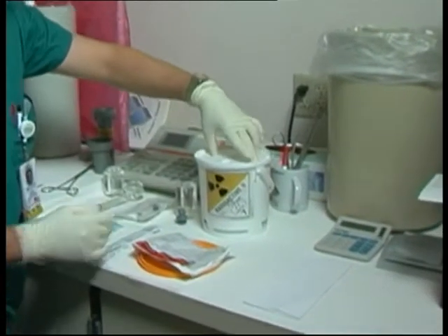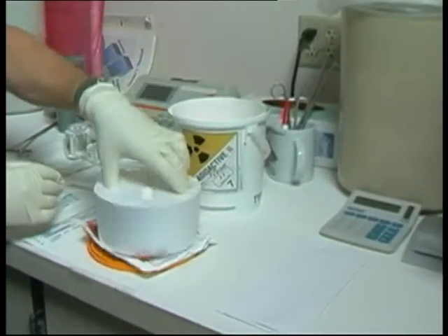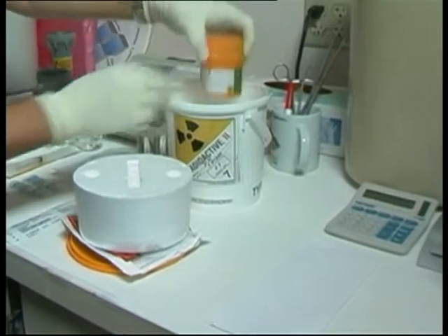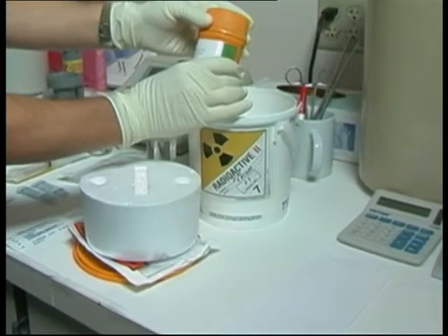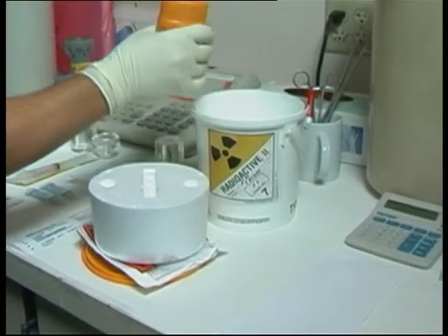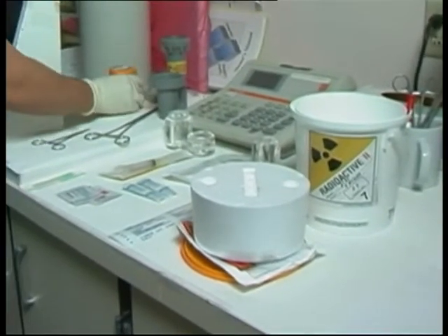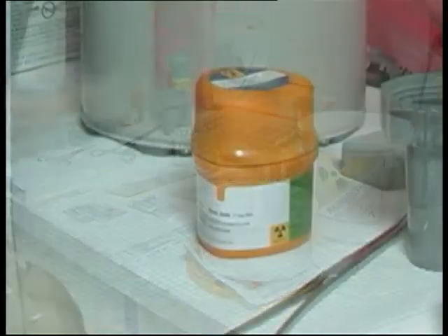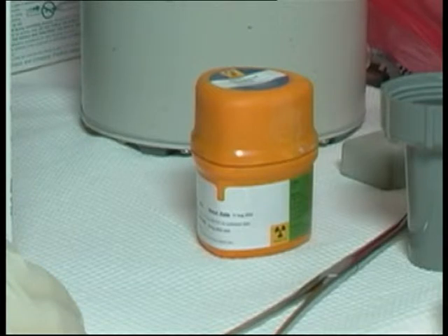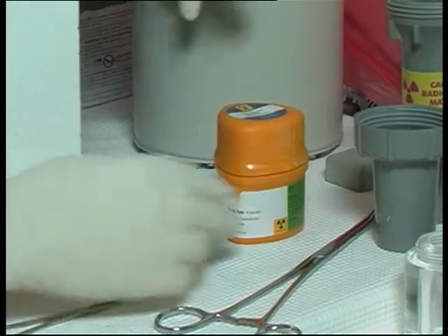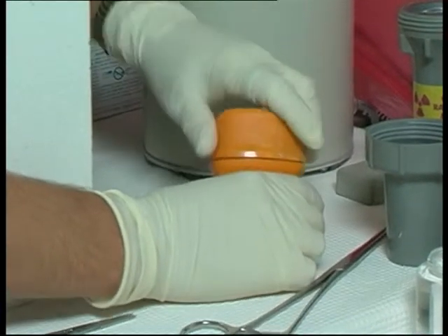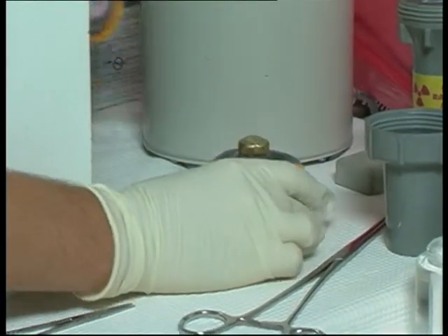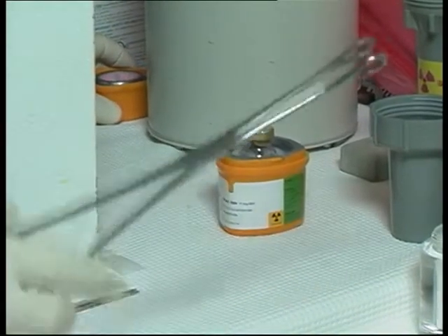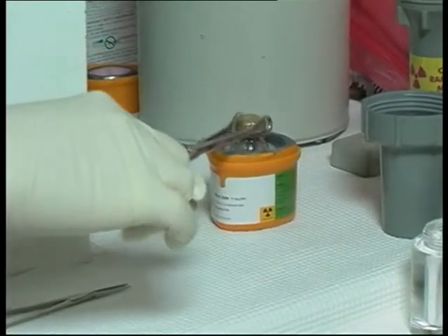SIR spheres will be shipped in an approved container. The SIR spheres shipping vial will be in a yellow lead pot to provide protection from radiation. Remove the lead pot from the shipping container and place it behind the L-block and acrylic shield. Check the label on the lead pot and vial to verify and confirm the calibration date is correct. Use tongs to remove the SIR spheres shipping vial and invert the spheres until they are fully suspended.